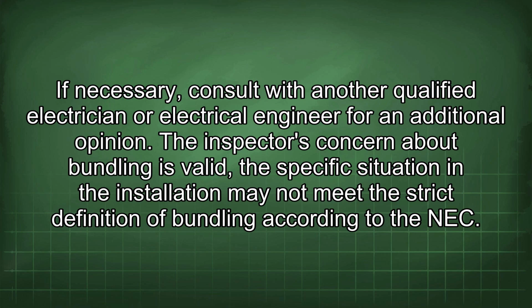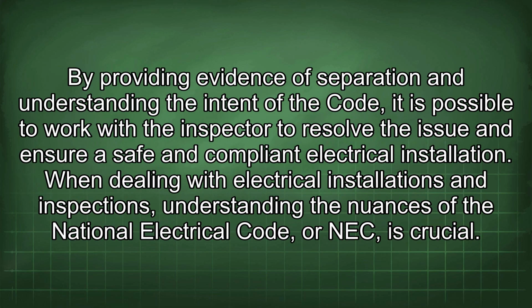The inspector's concern about bundling is valid. The specific situation in the installation may not meet the strict definition of bundling according to the NEC. By providing evidence of separation and understanding the intent of the code, it is possible to work with the inspector to resolve the issue and ensure a safe and compliant electrical installation.